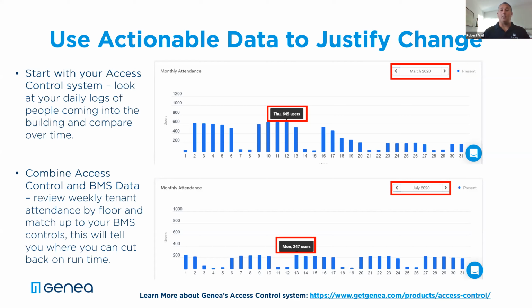Beyond that, you take the access control data and combine it with what you know about the building management system. If I see a trend based on the access control log of which tenants are coming in by which floor they occupy, maybe I run a recurring request based on the BMS and shut off the rest of the building. You can use the two data points together to operate the building more efficiently, and you're using data to justify that.